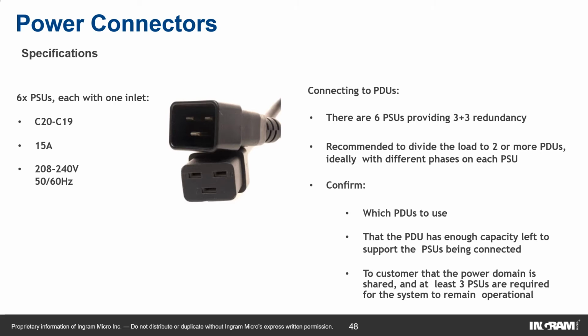There are 6 power supplies in the system providing N+N redundancy, each with one inlet supporting C20, C19 cables, 15 amp up to 240 volts of power. Before you proceed with the installation, confirm which PDUs would be used. Ideally, you would need 2 different PDUs for connecting the systems, and at least 3 power supplies need to be functional for the system to be operational.